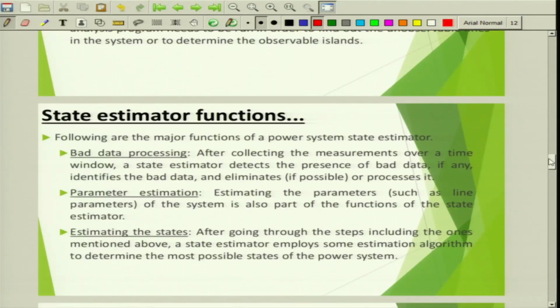Following are the major functions of a power system state estimator: bad data processing, parameter estimation, and estimating the states. After collecting measurements over a time window, a state estimator detects the presence of bad data, identifies it, and eliminates it if possible, or processes it. The first thing is you have a lot of junk data, and you need to take out the data which is not relevant — that is what bad data analytics is all about.